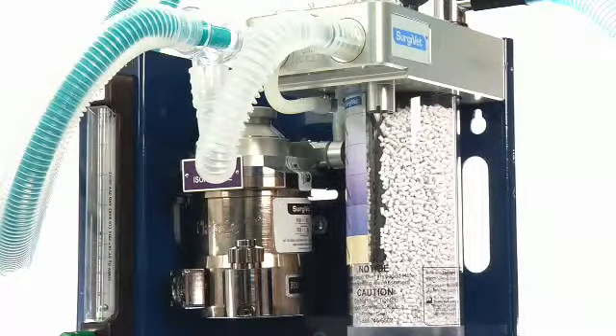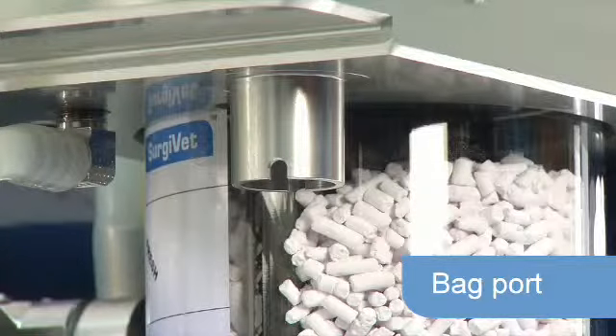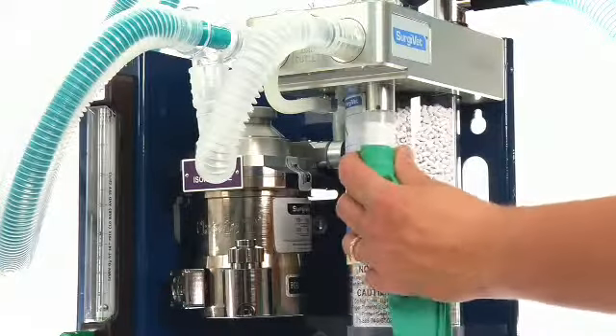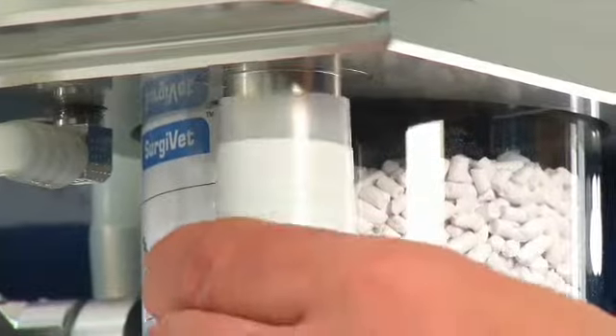Below the exhalation valve, on the underside of the machine, is the patient bag port. This port is used to connect a breathing bag or ventilator hose connection to the machine. The absorber canister is located behind the bag port. This canister holds the absorbent that removes CO2 from the recirculating anesthetic and oxygen. Behind the manometer is the pop-off valve.